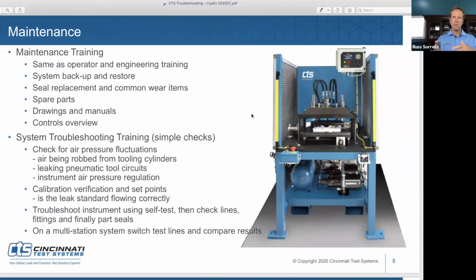So when you go to run the test, if it's not in that window, the instrument gives you an error. There's a test pressure low or a test pressure high error. Oftentimes that confuses customers, because they say, it's hitting the pressure, but as soon as it goes into stabilization, the pressure starts to go down a little bit and drops below the minimum pressure. And of course that triggers a fault in the instrument. So it's important that we have an appropriate plus or minus window on our pressure. I always target 10% with customers, 10% up or down.